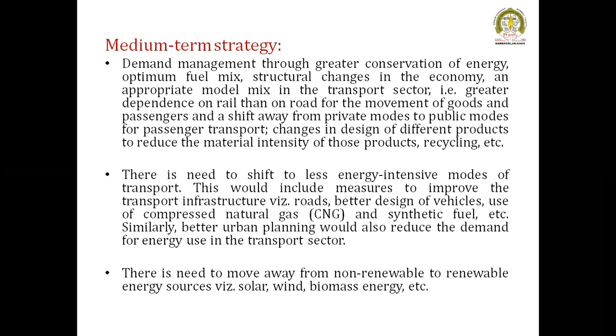The smaller the maximum demand, the lower the relative cost of generation. So if your load factor is small, the generation cost will be more, and if your load factor is toward unity, the cost of generation per unit becomes smaller, because the cost of production is spread over the number of units generated by the generating station. So in medium term strategies, we have to adopt demand side management in every sector, and this can be done with the help of tariffs, because tariffs play a very important role in demand side management.